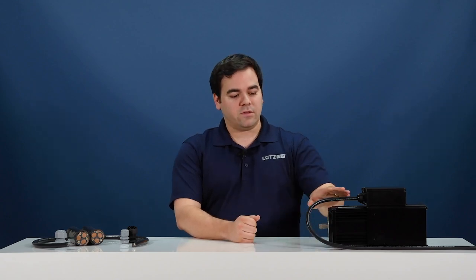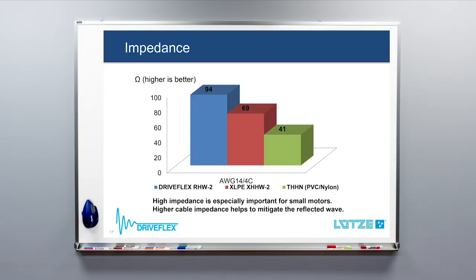How do we make the cable impedance higher? There are two factors that go into the impedance value for drive cable. The first is the insulation material used, and the second is the relationship of the conductors to one another — the actual geometry of the cable. Lutze DriveFlex uses an XLPE thermoset type insulation. In testing, we've shown that XLPE can have an impedance value as high as two times that of PVC nylon insulated cable. This significantly reduces the difference between the cable impedance and the motor impedance and helps minimize the reflected wave.